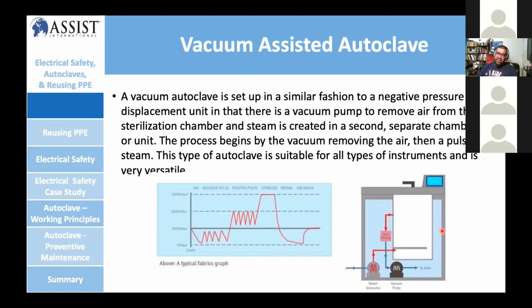Then vacuum assist autoclave. So with vacuum assist, there's a sterilization chamber and steam. What happens is a negative pressure displacement unit. So it's going to create a vacuum. There's a vacuum pump, the black one we see, that is going to remove all the air from the chamber. Once it removes air from the chamber, steam is created and goes into the chamber, and the process begins with a pulse of steam and pressure. This type of autoclave is very suitable for instruments. Most of the instruments they use are very commonly used in hospitals.